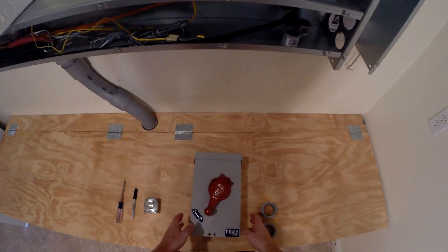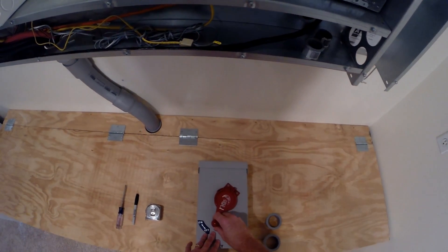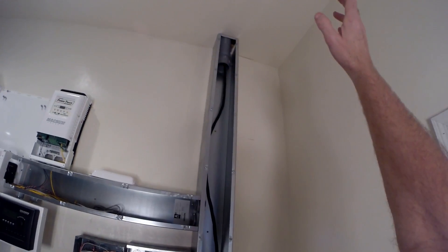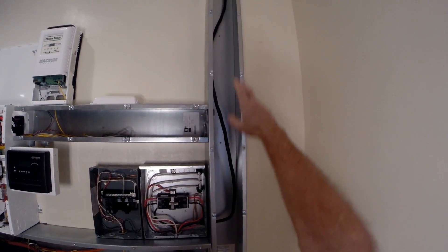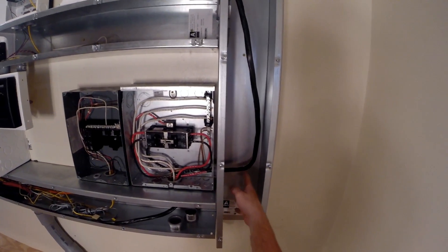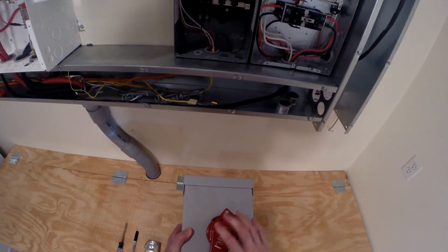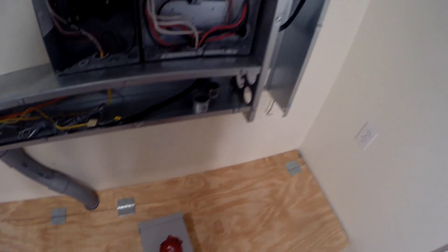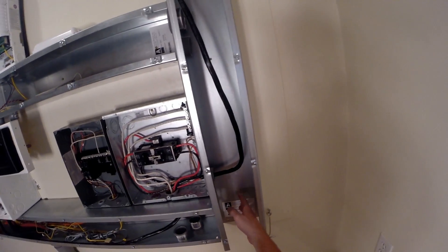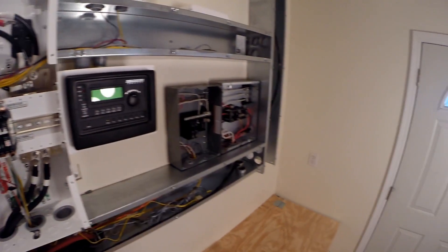What we're going to do now is install two of these combiner boxes - the Midnite Solar MNPV6 with a disconnect. We got about 14 wires coming from the panels with H4 connectors. They'll come down and feed out through the outside wall because I want these combiner boxes mounted on the outside wall so the fire department can get to them easily and cut them off in case there's a fire. Then the combined PV comes back through this PVC through the wall and splits through the six by six cable trays to go to the chargers or through breakers.